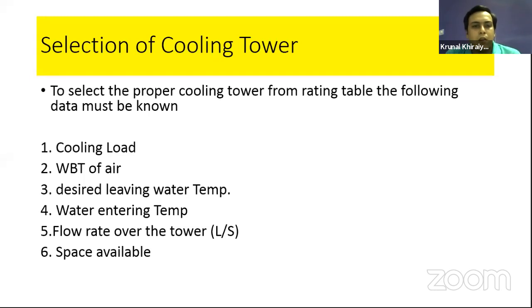And for the selection of a cooling tower, you must collect this much data beforehand. Cooling load: what cooling load you need to serve for the different processes. Then the wet bulb temperature of air. Then what temperature you are looking for as the cooling water outlet from the cooling tower. What is your water entering temperature? Then flow rate over the tower. Here I am mentioning L/s, meaning how much quantity is reserved with you so that evaporation from the water can take place. If you have scarcity of water, then this is a very important factor which can affect the selection of the cooling tower. And last, very important, space availability.